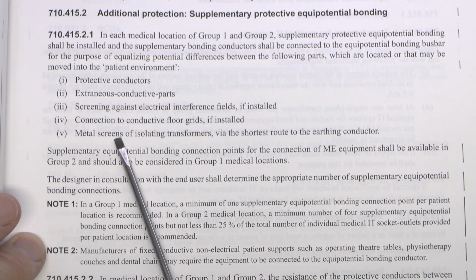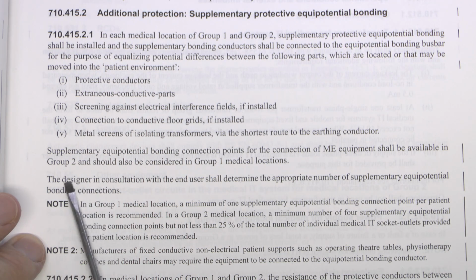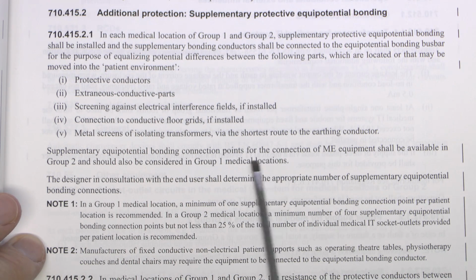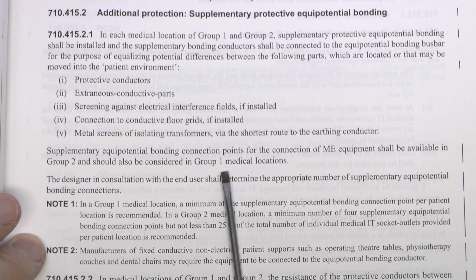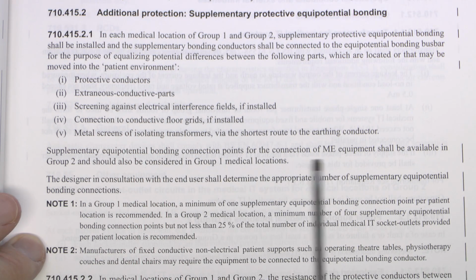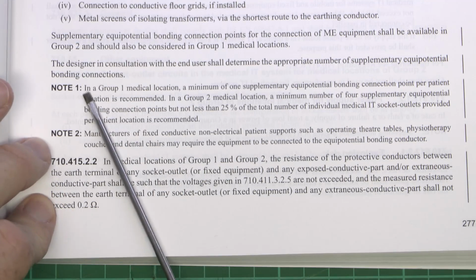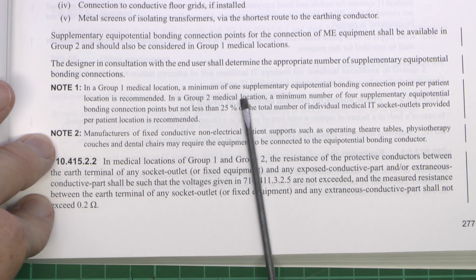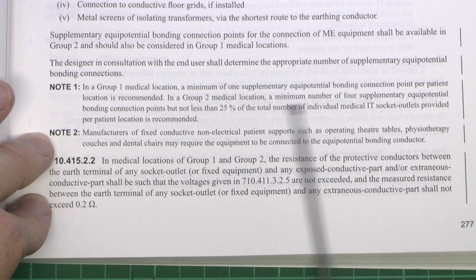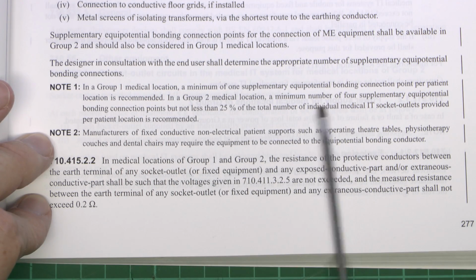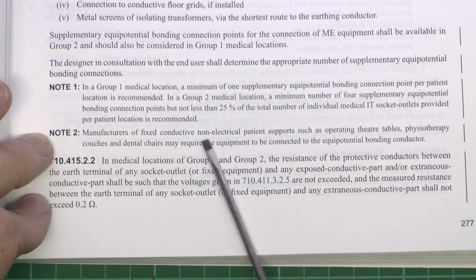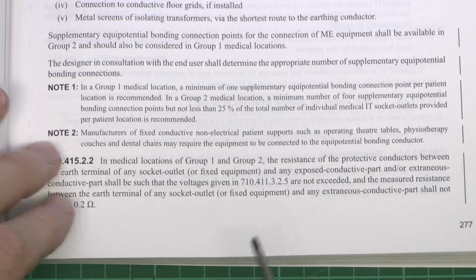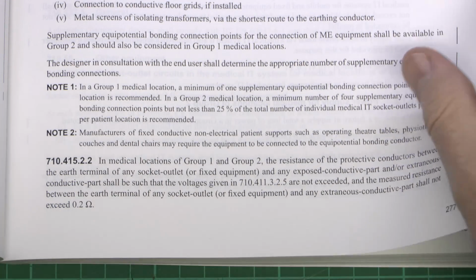710.415.2.1, substantially similar, though some rearrangement. The new part here is that supplementary equipotential bonding connection points for the connection of ME equipment shall be available in Group 2 and should also be considered in Group 1 medical locations. Previously this actually stated you should have a certain number of the connection points in each group location, so now it's just a question of having a certain number available. And then down here we've got notes 1 and 2, which again are taken out of the original text, and this just gives you a suggestion, so a minimum of 1 per patient location is recommended, and again for the group 2, a minimum of 4. So substantially quite similar, but it's just a question of rearranging and putting things into notes, which were obviously not in that arrangement before.